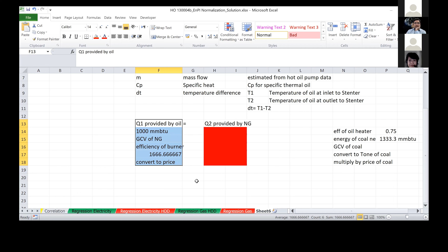Now there are normally 2, 3, or 4 heat exchanger points. In some stenters, we have even 8 or 9 chambers. So for each chamber, we have heat exchange points. We can either calculate separately for each of these, but before and after this stenter, we have distribution points where the oil is getting distributed. So at the intake, there's one small header which distributes thermal oil to the multiple chambers of the stenter. So we need to measure the oil temperature before this header where it is further divided. And then when it comes out of all these chambers, it combines into one line afterwards. Not all the lines go all the way towards this oil heater. They all combine into one line afterwards. That is where we need to calculate the temperature. So that is how we calculate the overall delta T.